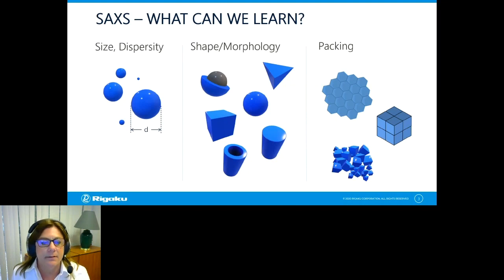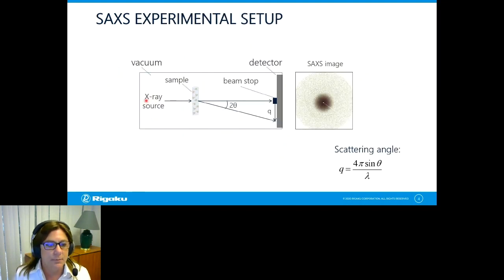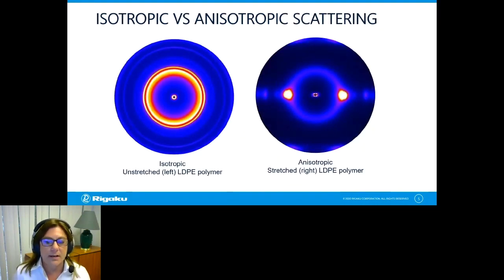So what does a typical SAXS experiment look like? Well, it looks like this. So SAXS instruments, of course, have an x-ray source, a downstream sample holder. Downstream of that, we have a detector and a beam stop. And the beam stop may be monitoring the beam intensity throughout. And this is often carried out in a vacuum. So during the sample experiment, x-rays are mostly transmitted in a, are mostly exposing the sample in a transmission mode. And then we see scattering, like the example image you see to the right. And in this case, for this example, you'll see on the bottom, the relevant scattering angle. So if you've done XRD before, you probably talk in 2 theta. For x-ray scattering, we talk in Q, which expresses the scattering angle in a wavelength dependent manner. So here's an example SAXS image, and not all scattering experiments are exactly like that.